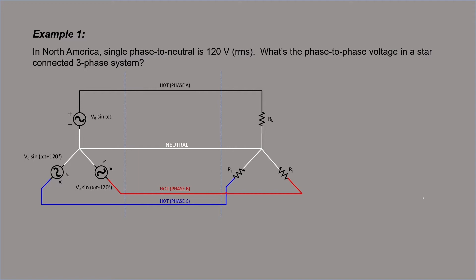We'll start off with North America. In North America, the voltage between a single phase and neutral is 120 volts RMS. What's the phase-to-phase voltage in a star-connected three-phase system? I've changed colors here because in North America, normally hot is black wire, white is neutral, and then if you have a three-phase system, the other two phases are typically either red or blue.